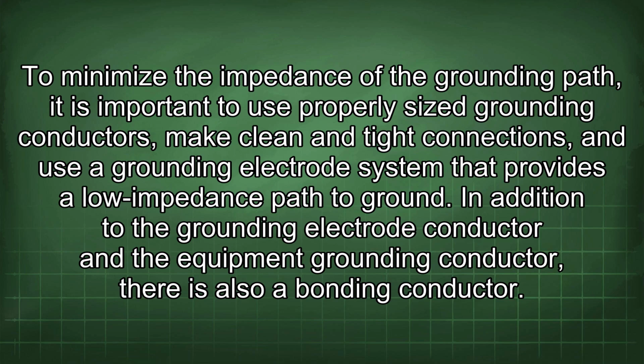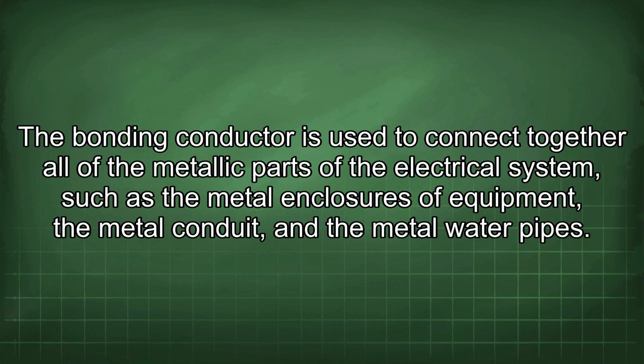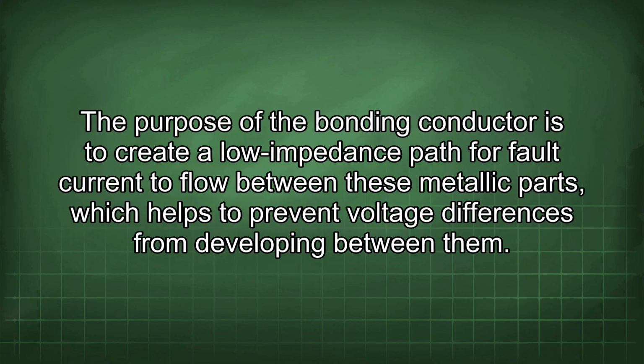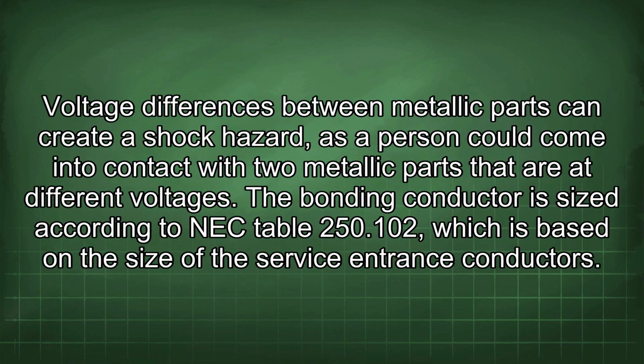In addition to the grounding electrode conductor and the equipment grounding conductor, there is also a bonding conductor. The bonding conductor is used to connect together all of the metallic parts of the electrical system, such as the metal enclosures of equipment, the metal conduit, and the metal water pipes. The purpose of the bonding conductor is to create a low impedance path for fault current to flow between these metallic parts, which helps to prevent voltage differences from developing between them. Voltage differences between metallic parts can create a shock hazard, as a person could come into contact with two metallic parts that are at different voltages.